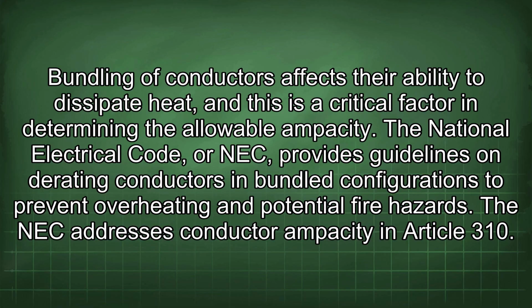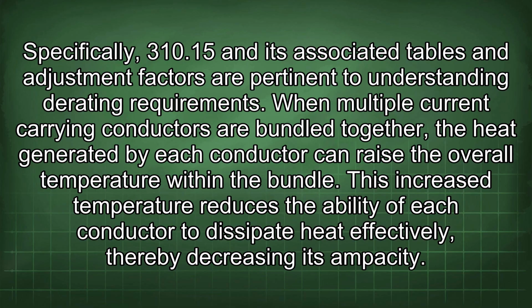The National Electrical Code, or NEC, provides guidelines on derating conductors in bundled configurations to prevent overheating and potential fire hazards. The NEC addresses conductor ampacity in Article 310. Specifically, 310.15 and its associated tables and adjustment factors are pertinent to understanding derating requirements. When multiple current-carrying conductors are bundled together, the heat generated by each conductor can raise the overall temperature within the bundle. This increased temperature reduces the ability of each conductor to dissipate heat effectively, thereby decreasing its ampacity.